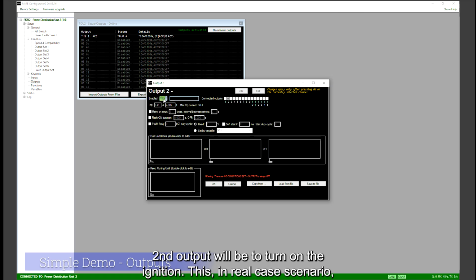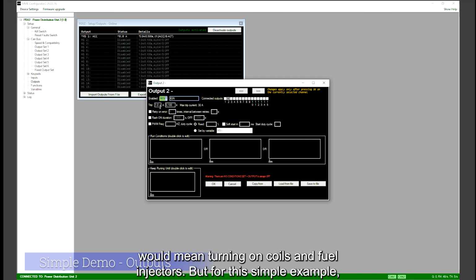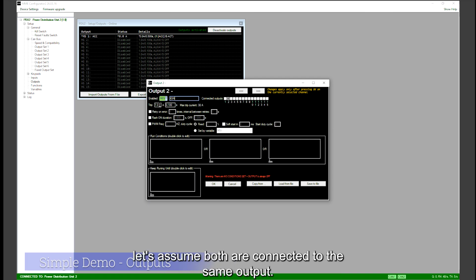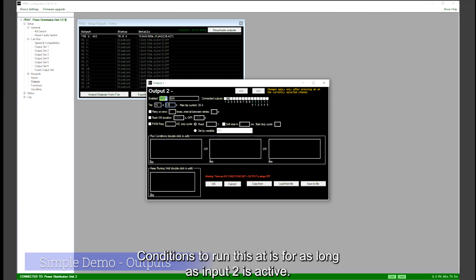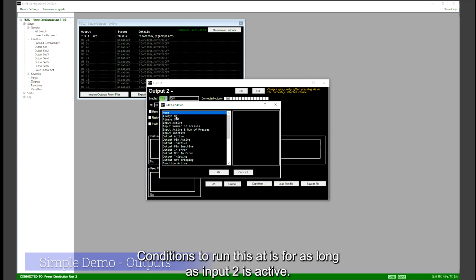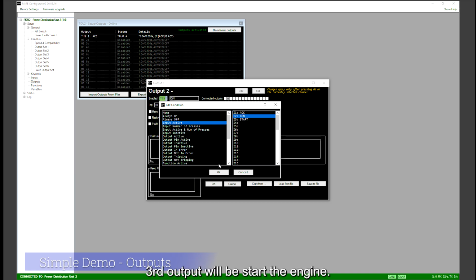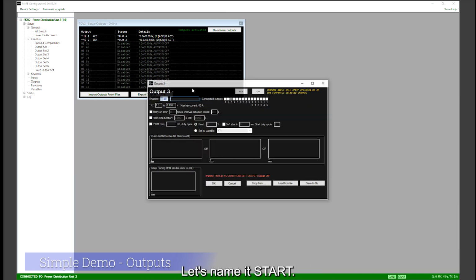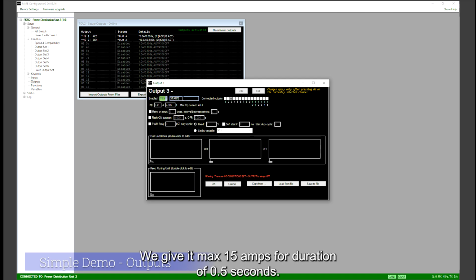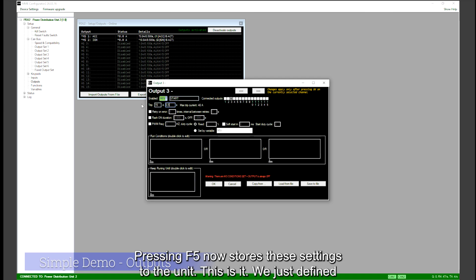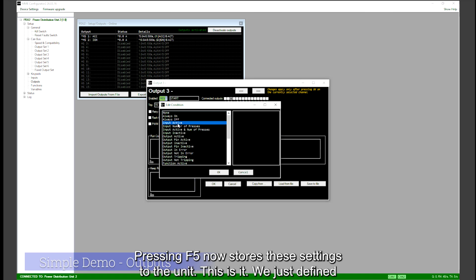Second output will be to turn on the ignition. This, in a real case scenario, would mean turning on coils and fuel injectors, but for this simple example, let's assume both are connected to the same output. Let's say trip current is 10 amps for the duration of 0.5 seconds. The condition to run this is for as long as input 2 is active. Third output will be to start the engine. Let's name it Start. We give it max 15 amps for a duration of 0.5 seconds. Pressing F5 now stores these settings to the unit.